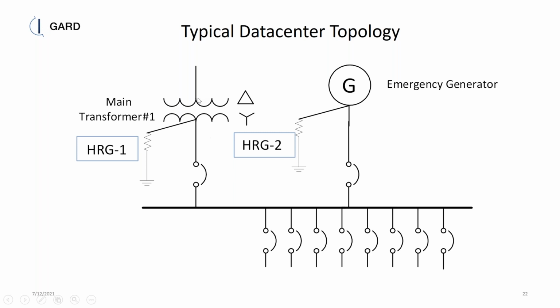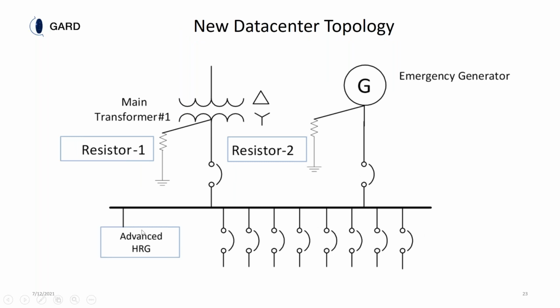So once you lose utility, we switch over to generator. When we switch over to generator, we're feeding the system here. So we're sharing the loads between either the transformer or the generator. Typically, the generator is in a different building because it's noisy and you want to be away from the environmental conditions of the data center. So if there's a utility fault, the HRG system is going to be looked at for the utility, and the HRG system is going to be looked at for the generator, depending on what source is on. With the iGard solution, it doesn't matter which source is in the circuit. The fault current is always going to return back to the source which is active.